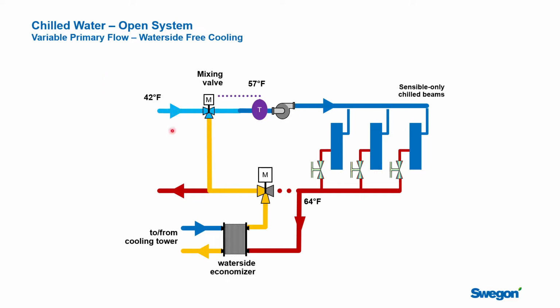The chiller plant would be completely shut down. There would be no need for chilled water for the air handling units because it would be cool enough outside that that wouldn't be a challenge. And so this loop would just run like this, and the main chiller plant would all be shut down. In shoulder weather, you might be able to do some free cooling here and mix it with the chiller plant if it's online. If we may not be able to get it all the way down to 57 degrees, we could introduce a little bit of chilled water from the chiller plant to do this.